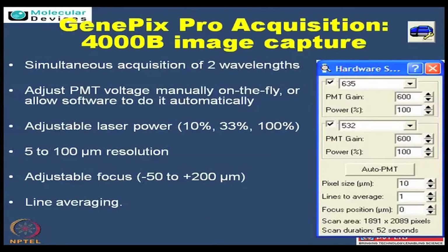There is a button towards the side where you have control for the scanning time. As it is a dual channel, meaning two lasers are present, it allows you to select whether you want to use 1 and 2. Based on the user application, you select both lasers, and then at the level of the scan, you control the PMT and which resolution you want to use. These are all within the same software.